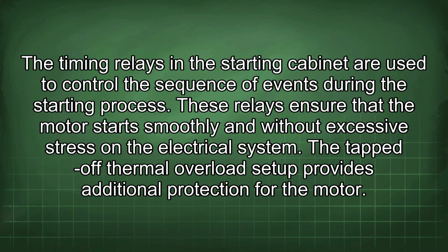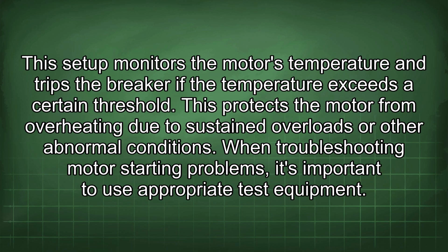The timing relays in the starting cabinet are used to control the sequence of events during the starting process. These relays ensure that the motor starts smoothly and without excessive stress on the electrical system. The tapped-off thermal overload setup provides additional protection for the motor. This setup monitors the motor's temperature and trips the breaker if the temperature exceeds a certain threshold. This protects the motor from overheating due to sustained overloads or other abnormal conditions.